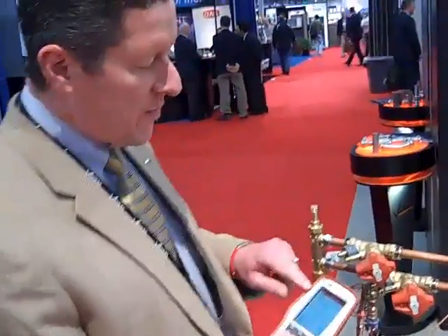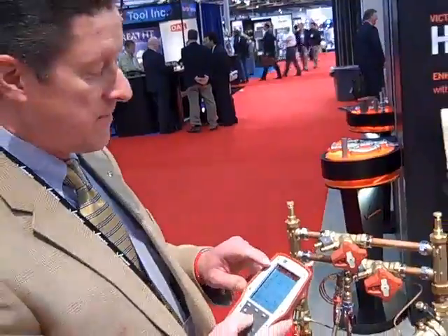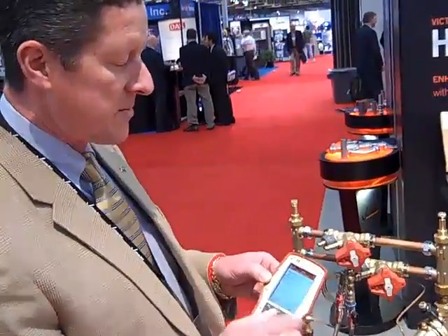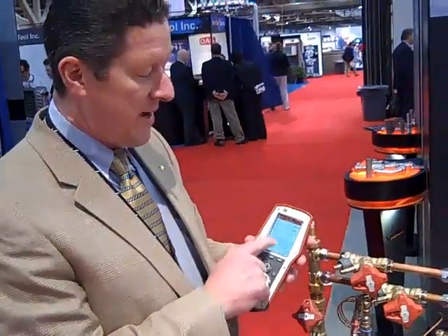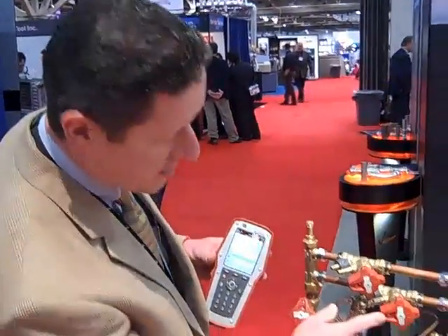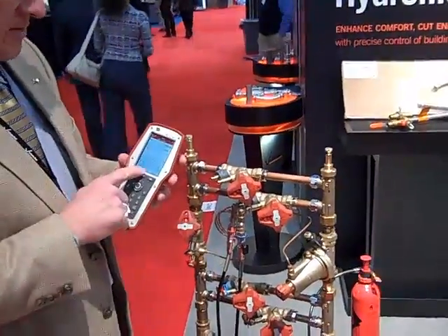So first thing we're going to do is hit quick measure here. And when we do that, it comes up. We have the option of checking flow, differential pressure, temperature, and even power. So we can actually measure the power usage on a circuit with this unit. If we hit measure flow, this is our design data here, so we have it set for 1 GPM. That's what the engineer has specified. We have a 1/2 inch TA valve. It's set currently at 2 hand wheel turns, and the media is water.